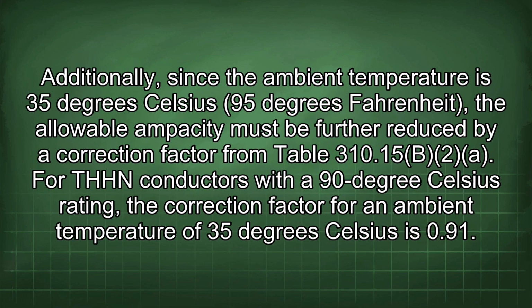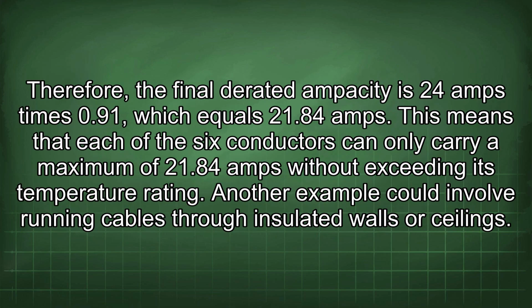Additionally, since the ambient temperature is 35 degrees Celsius (95 degrees Fahrenheit), the allowable ampacity must be further reduced by a correction factor from Table 310.15(B)(2). For THHN conductors with a 90 degrees Celsius rating, the correction factor for an ambient temperature of 35 degrees Celsius is 0.91. Therefore, the final derated ampacity is 24 amps times 0.91, which equals 21.84 amps. This means that each of the 6 conductors can only carry a maximum of 21.84 amps without exceeding its temperature rating.